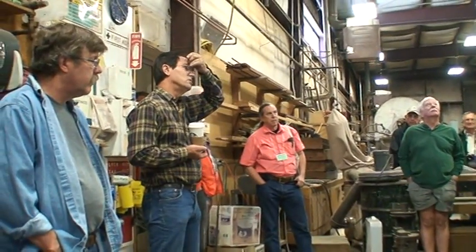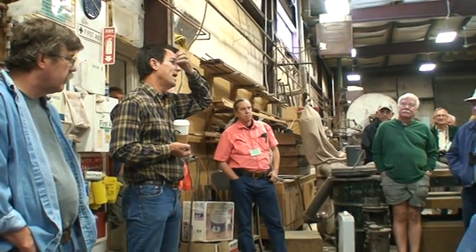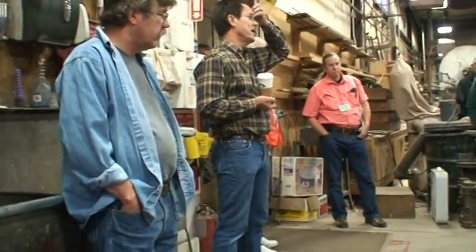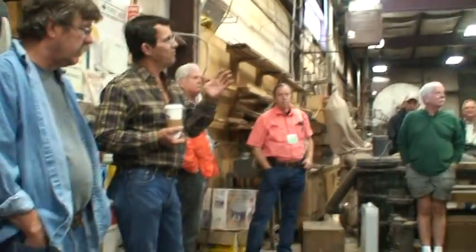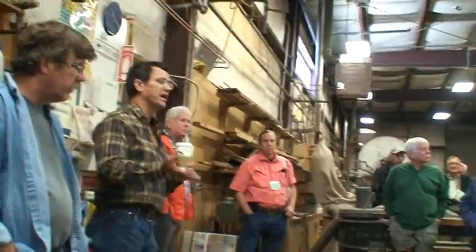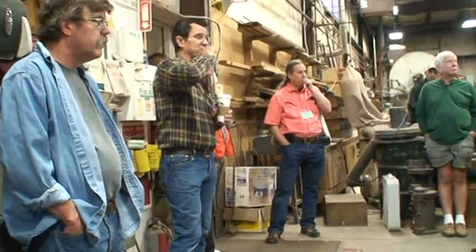And we were talking about boilers and I talked to him about the 22 up front, which operates at 75 pounds. He said, we would never do that in Canada. He said, in Canada, our philosophy is if you have a boiler and you can't get it to operate at its original design pressure, there's something wrong, fix it, or you won't run it. Boilers are not derated in Canada. They are either repaired to operational status or they are not licensed. Needless to say, we're going back to 130 pounds on this, original operating pressure.